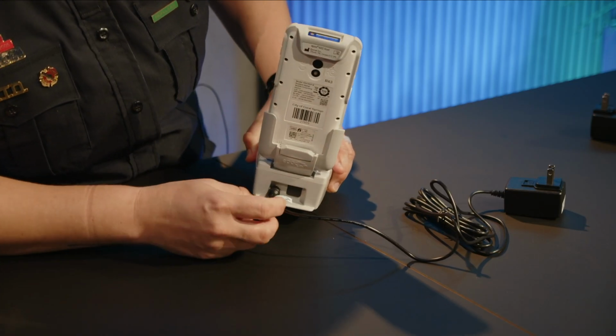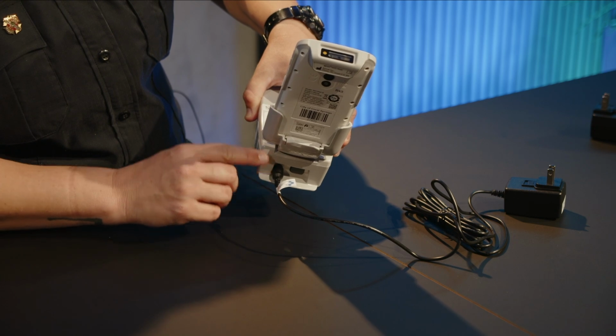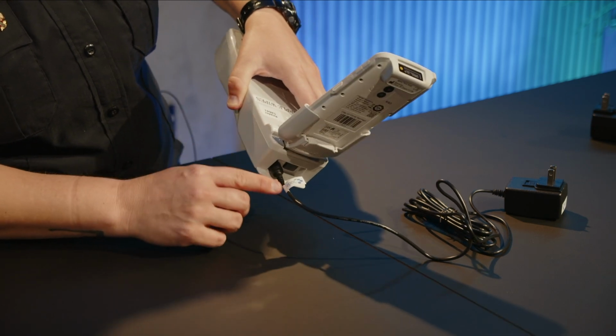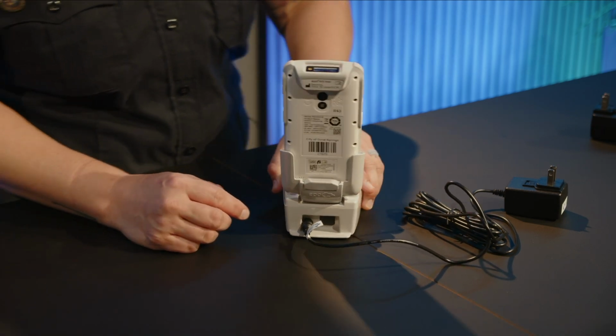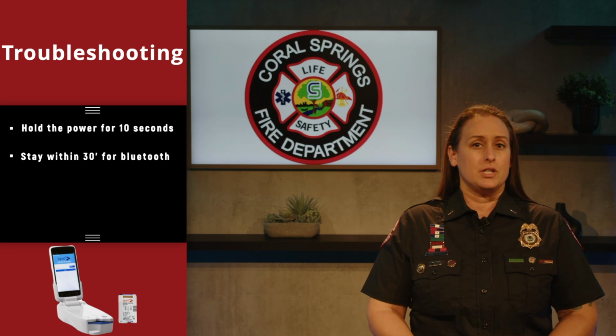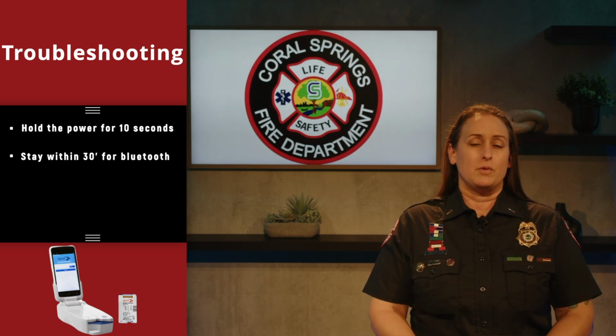Battery life is also something to keep in mind. The reader can run about 50 tests on a single charge, but to avoid interruptions, it's best to plug it in between uses whenever possible. Let's go over a few troubleshooting tips. If the reader or the host becomes unresponsive, try holding the power button down for 10 seconds to restart it. If you're having Bluetooth issues, make sure both devices are close together and try turning them off and back on. If an error message pops up, refer to the epoc system manual or reach out to your supervisor for guidance.